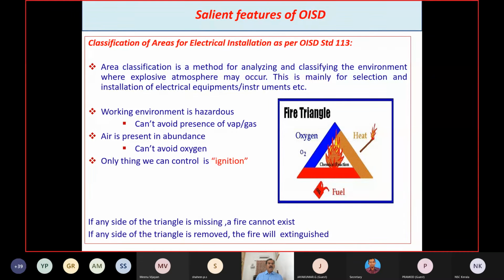Actually, the hydrocarbon gases and the air both should be in the right proportions. The explosive atmosphere is nothing but hydrocarbon vapors or gases and air, so it should be in the right proportions. The right proportions means it should be between the lower explosive limit and the upper explosive limit. That is the explosive limit range. So we should know what LEL and UEL are.